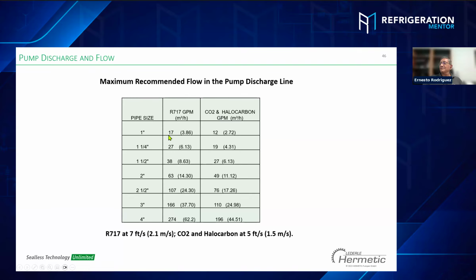1 inch, for example, is good to handle 17 gallons per minute. If you go over 17 gallons per minute, you go to the next size, 27 gallons per minute. The same way for CO2. For CO2, 1 inch on the pump discharge is the maximum, handling 12 gallons per minute, all the way to 4 inches. Now, 196 gallons per minute for CO2 and 274 gallons per minute for ammonia.